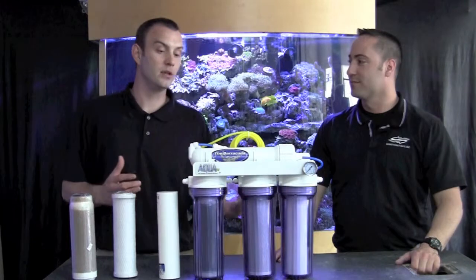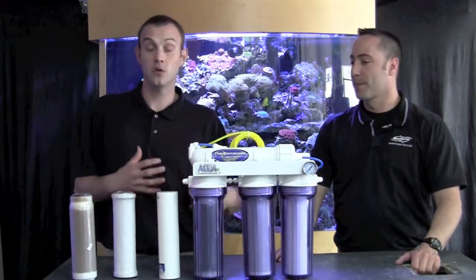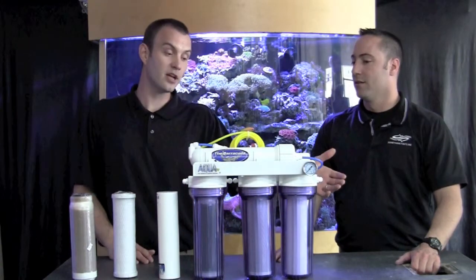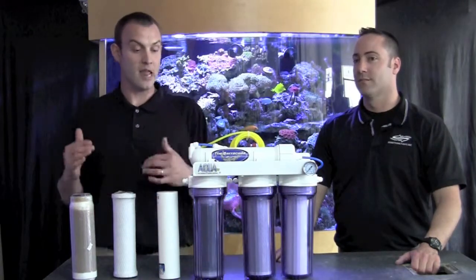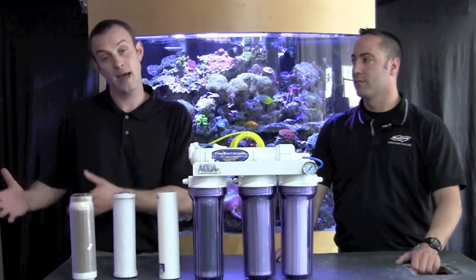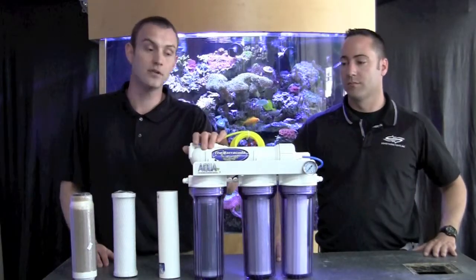Ultimately you're going to want to be looking at your total dissolved solids — that's how you test to see if the unit is functioning well or if your filters need to be changed. You're going to want to test your incoming water supply and then your outgoing water supply and see what the difference is. If you get any readings above 10 parts per million of TDS on the back end of your filter, then you know it's probably time to change either your DI filter or your membrane.